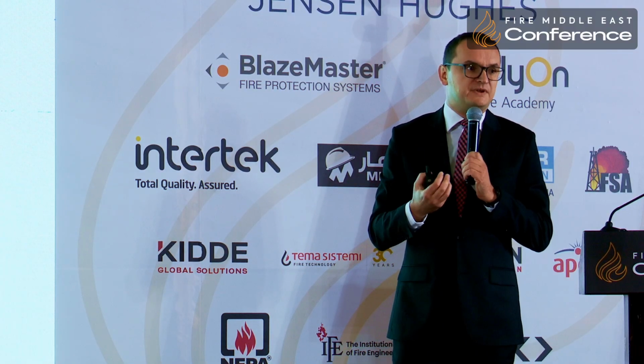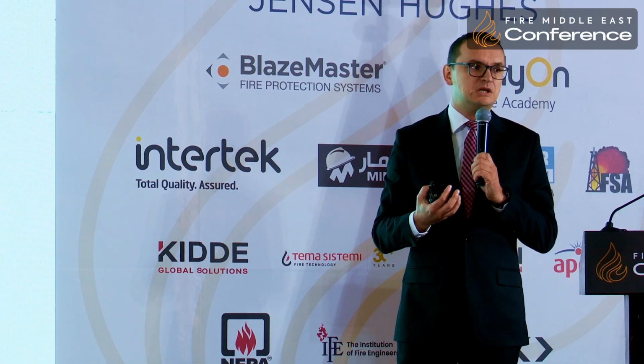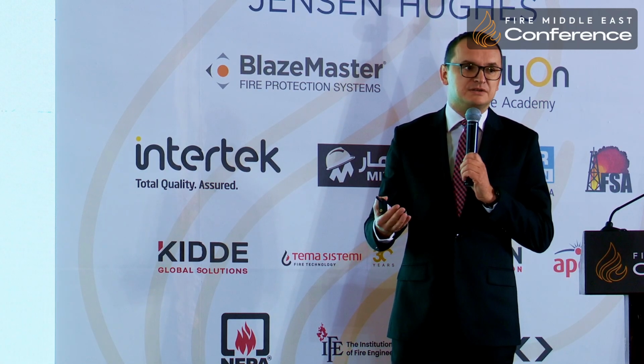Also, in recent communication we became aware there were some attempts to use insulation material for ducts that is already containing some carcinogenic substances. That situation may be motivated financially, as this type of material might be cheaper, but on the other hand, think about the practical implications. Testing can be done, but will require more measures to be applied at that stage, more cleaning after that stage, and assurance that people are taking proper measures. But imagine also handling, installing, and making sure that it can be properly maintained on site. There would be additional costs, even if it's not restricted by law, and at some point it might be restricted and may be requested to be removed from buildings.